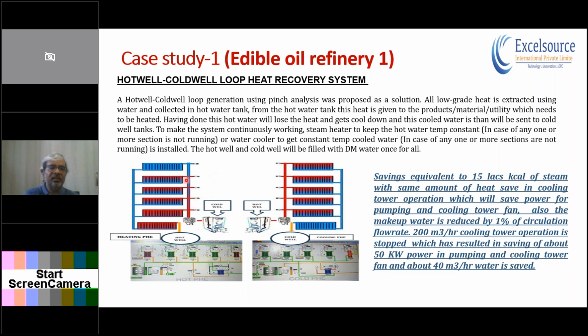If you see my screen, my cursor, we have extracted heat from the heating PHE. We have mentioned about 6 PHE on the heating side and 6 PHE on the cooling side. It is actually quite a complex plant. It is more than, I think, 20 to 25 PHE that we have installed all put together. We have collected the data and then developed this design.